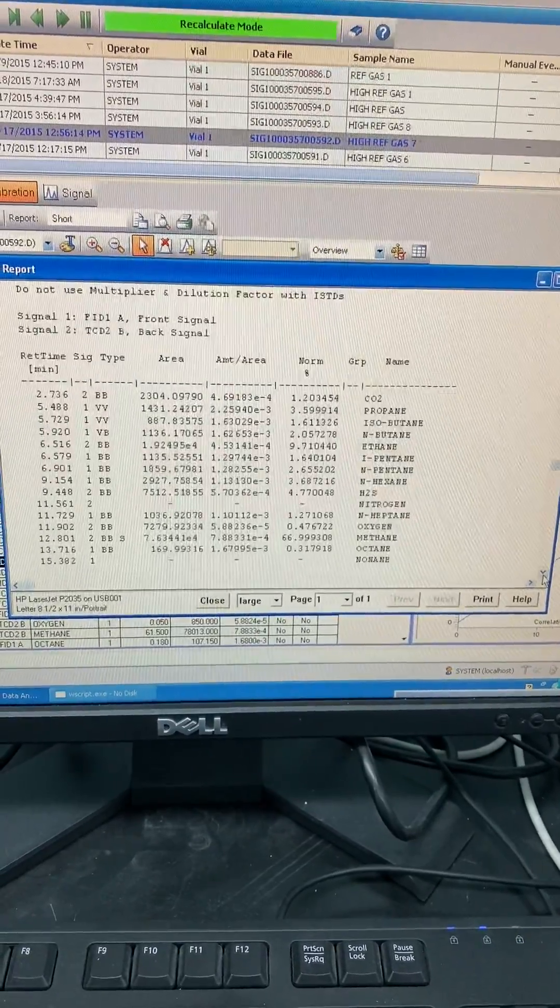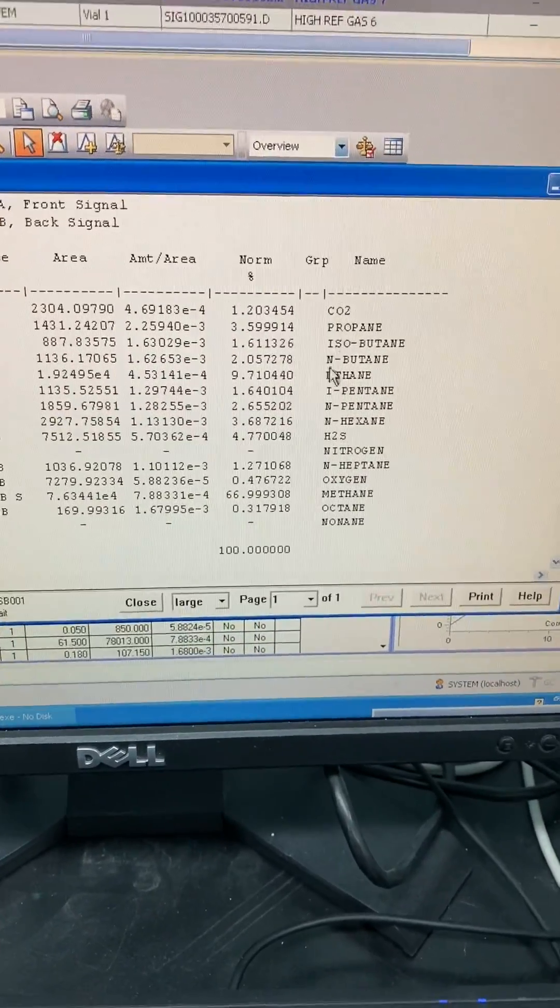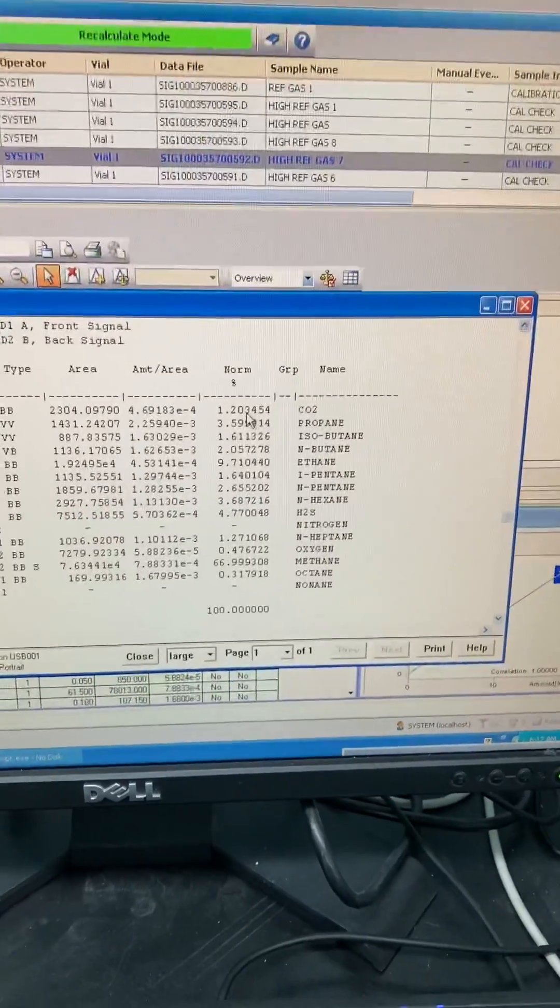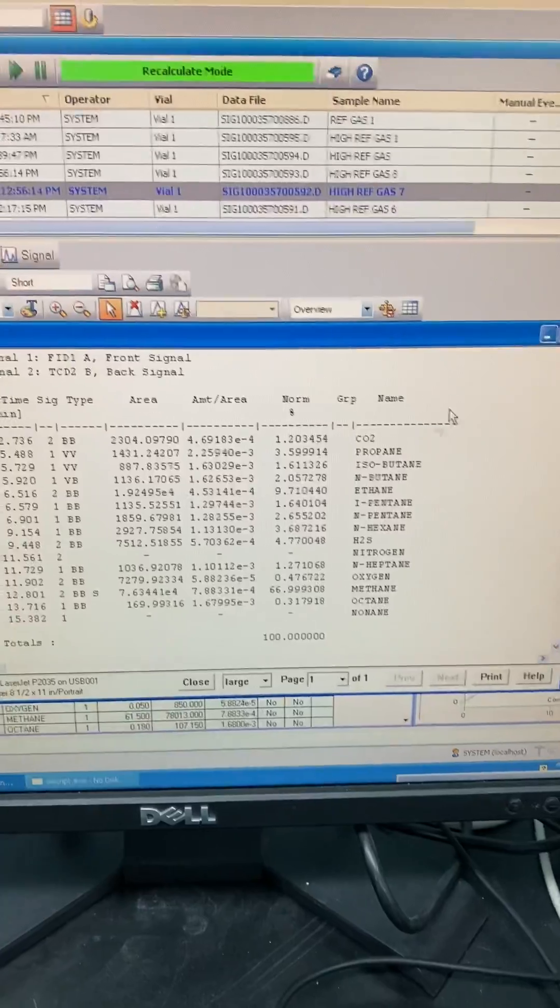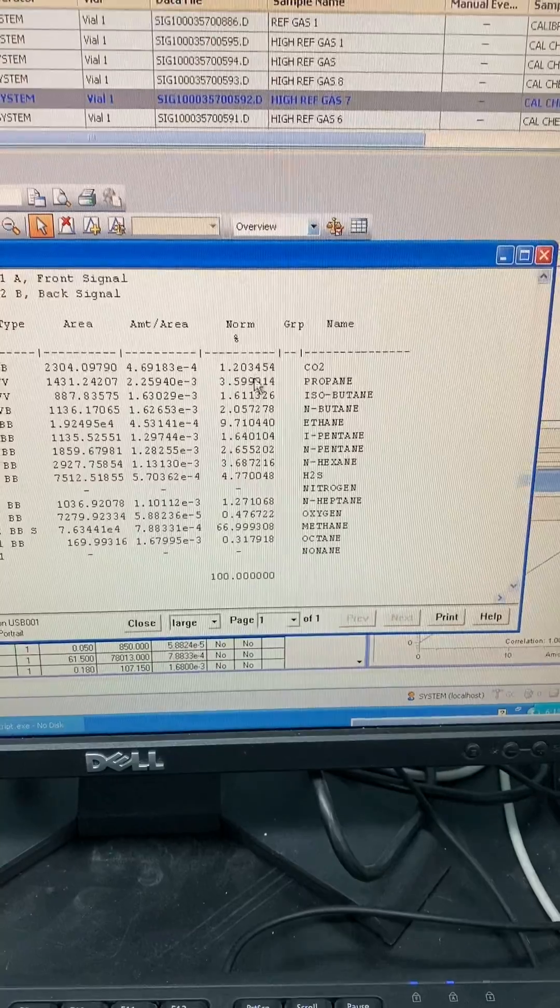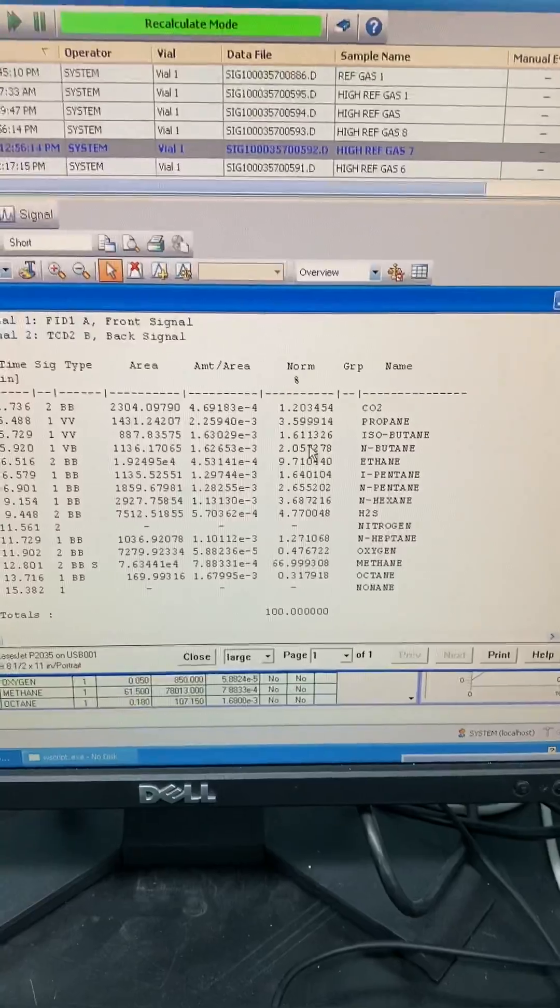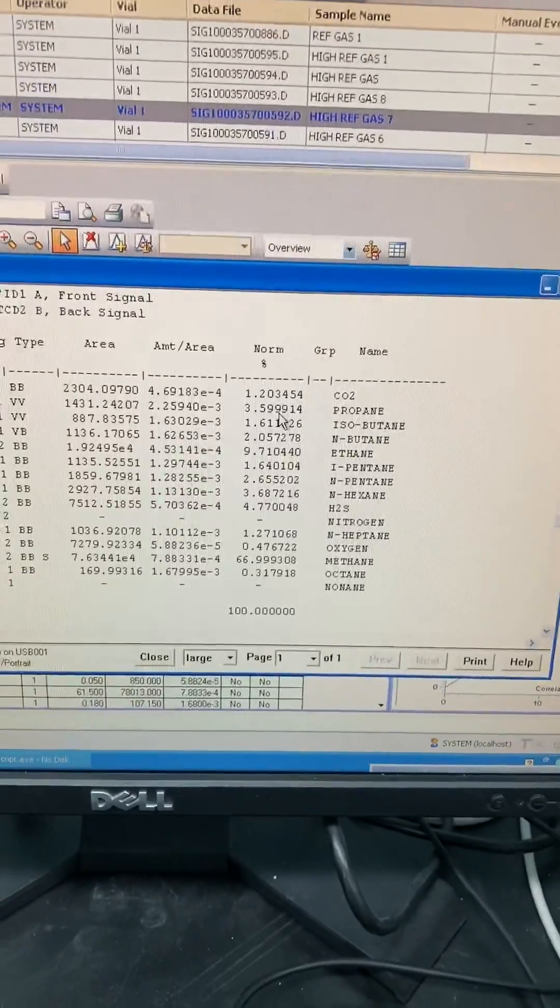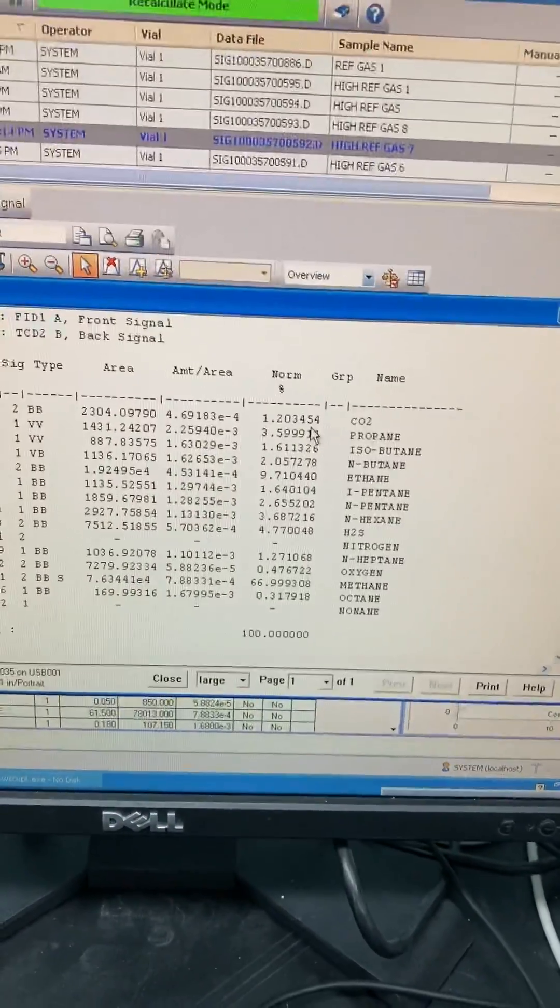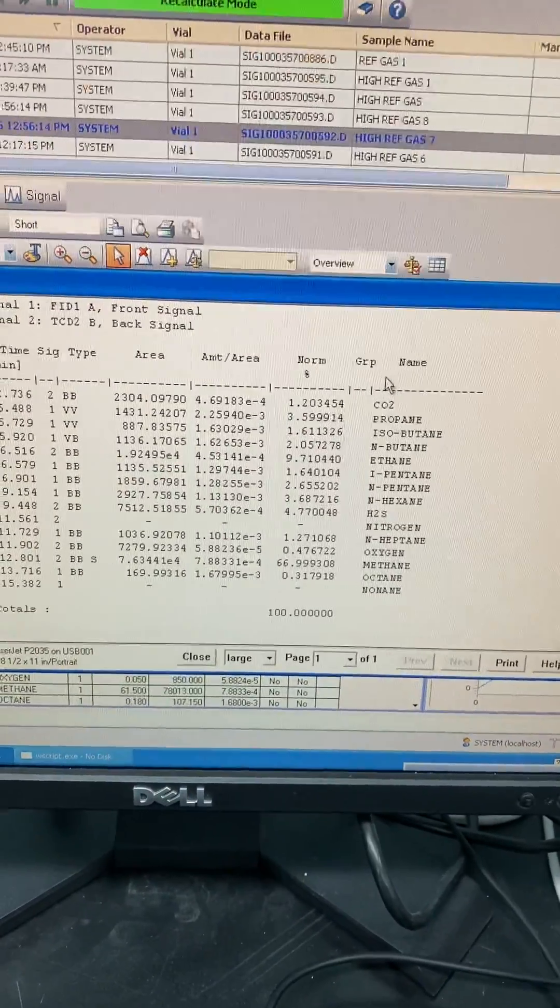So how to check my method is it calibrated or not? By comparing the final report with the certificate that came with the reference material. If I see the result here or the concentration of each component near to the certified reference material maximum 5 to 10% variation, that means the instrument is accepted or it's already calibrated and I can run my sample. If I found deviation from the concentration from this report and the certificate, I have to re-inject the standard several times, three to five times at least, to have three repeatable runs. When I'm saying repeatable, that means all the concentrations are almost the same for the three runs, because you will select one of the run or two or three take average to make the calibration.